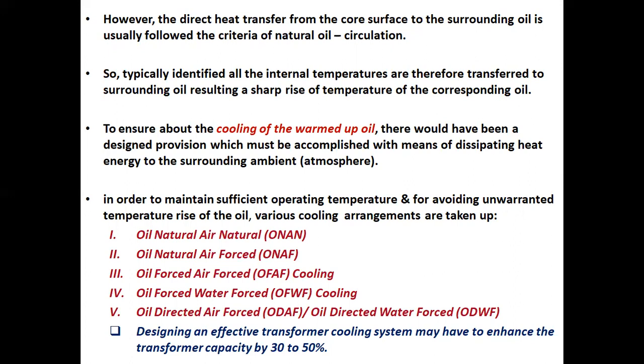In order to maintain sufficient operating temperature and to avoid unwarranted temperature rise of the oil, various cooling arrangements are taken up. One, oil natural, air natural, that is ONAN type. Number two, oil natural, air forced, that is ONAF. Number three, oil forced, air forced, OFAF. Number four, oil forced, water forced, OFWF. Number five, oil directed, air forced, ODAF, or oil directed, water forced, ODWF. Designing an effective transformer cooling system may enhance the transformer capacity by 30 to 50% of its capacity.